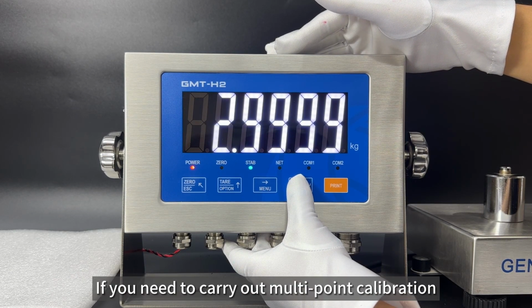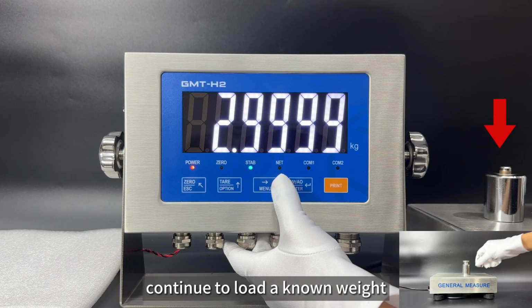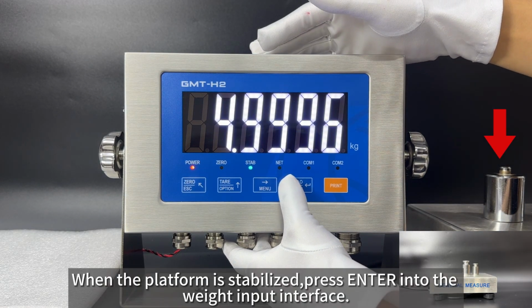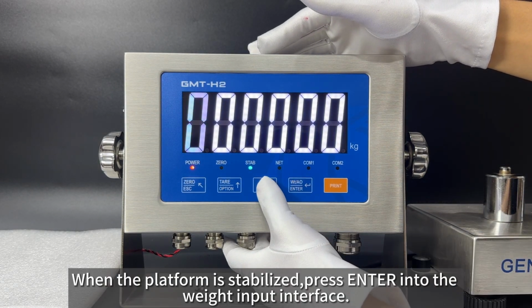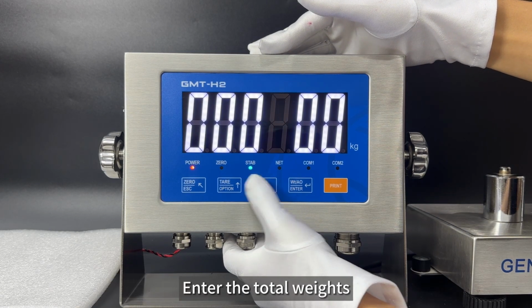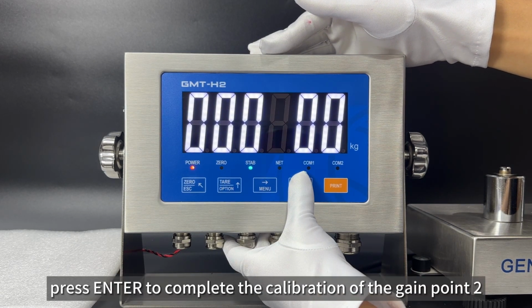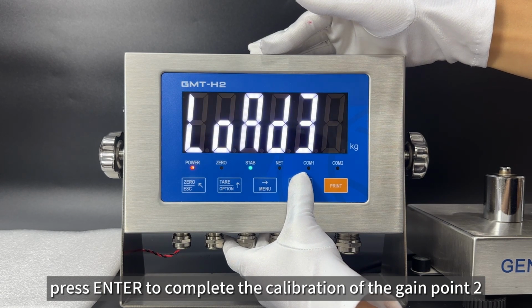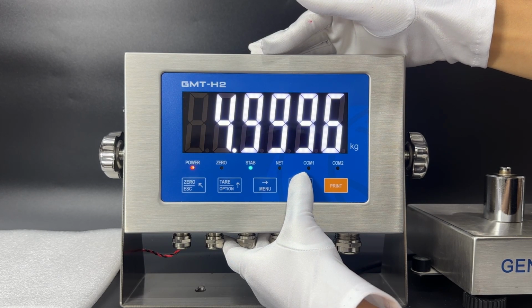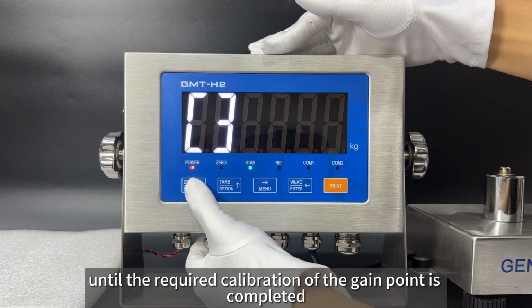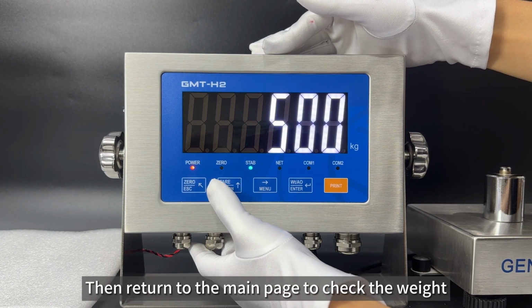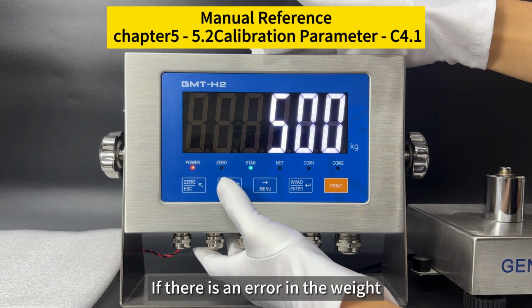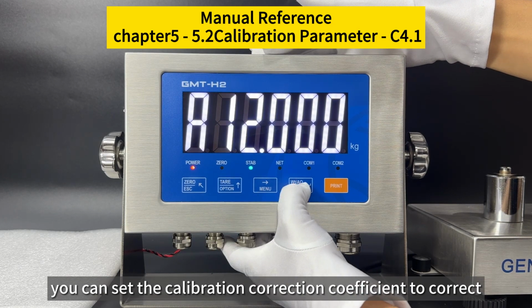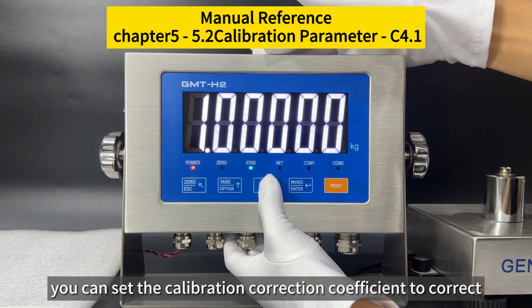If you need to carry out multi-point calibration, continue to load a known weight. When the platform is stabilized, press enter into the weight input interface. Enter the total weights. Press enter to complete the calibration of the gain point 2. Follow these methods until the required calibration of the gain point is completed. Then return to the main page to check the weight. If there is an error in the weight, you can set the calibration correction coefficient to correct.